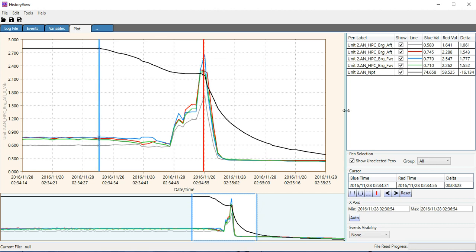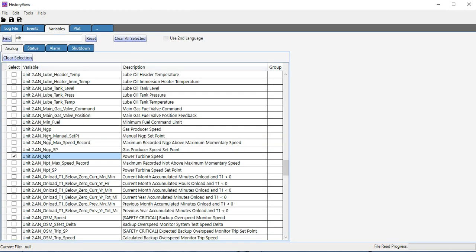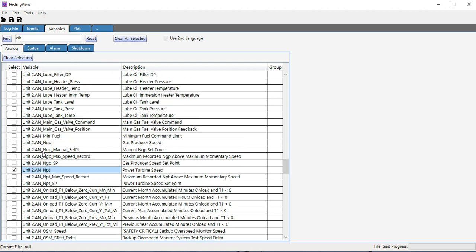So we can see that the vibration levels were pretty nice, smooth, steady, up to this deceleration, and out of the blue it seems the vibration spiked high. That's kind of unusual that vibration would spike high as speed was decreasing, and it doesn't look like a critical speed to me. So maybe something process related. Let's add a variable for surge margin on the compressor.